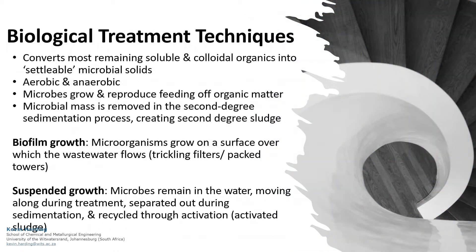Secondary treatment may also include physical methods, as well as biological treatment techniques. Any remaining soluble organics can be consumed aerobically or anaerobically and removed. Two types of microbial growth can occur: either through biofilm growth, where water flows over the microorganisms, or as suspended growth, where the microorganisms flow with the water during treatment.